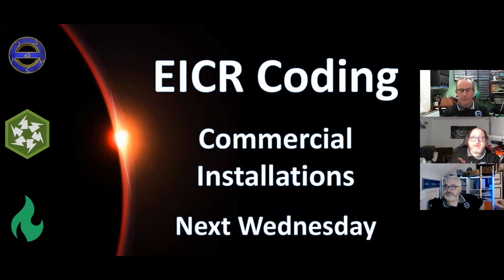Okay. He's got another one. Maybe not a coding issue, but a testing one on the calculation of Zs using Ze impedance in R1+R2. No parallel paths are taken into the measurement, so there's a lower fault current possibility. I personally still think a full Zs impedance test, but Electricity at Work Regs doesn't like this method. So we shouldn't do live Zs testing because Electricity at Work Regs doesn't want us to do live work if we don't need to do live work.